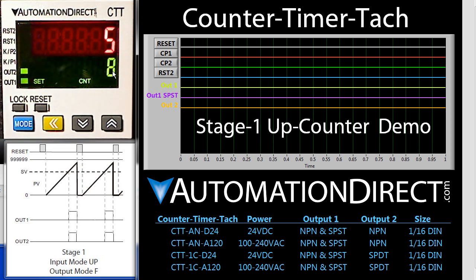The counter can operate in a number of different modes. This one is in mode F right now, which looks like this right here. The counter counts up, and when it hits the set point, both outputs toggle. The counter continues to count up until a reset is issued, which resets the counter and outputs.